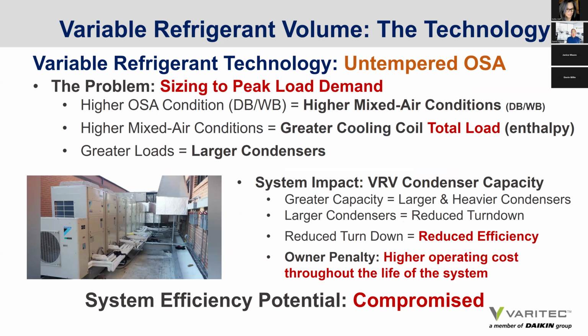So when you design a variable refrigerant system with untempered outside air, you have a higher outside air condition temperature, which means you have a higher mixed air condition at your fan coil cooling coil. That higher load at the fan coil means that condensers have to be oversized to meet the peak demand. Well, the problem is that when you design around larger condensers, you have reduced turndown. And it is during turndown that variable flow technologies offer their greatest advantage, when you're at part load. Reduced turndown means reduced efficiency. And consequently, the owner pays a higher operating cost throughout the life cycle of the building than with a more efficient design approach with variable refrigerant technology.